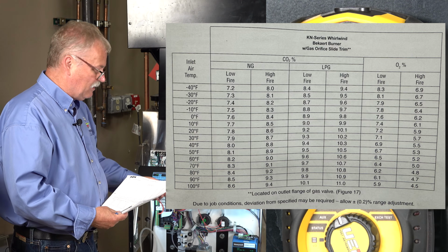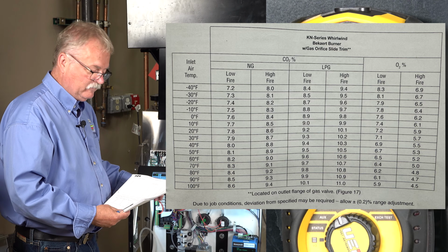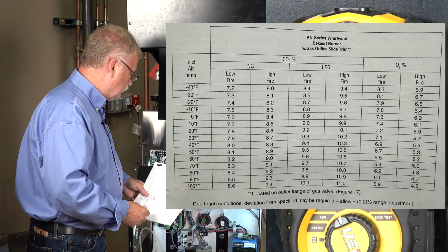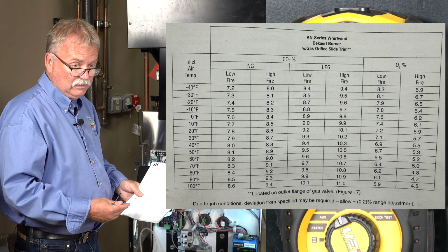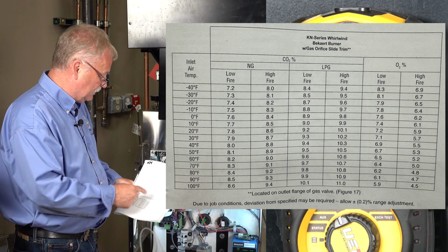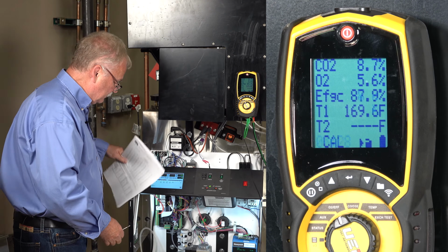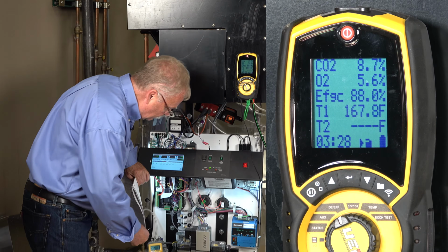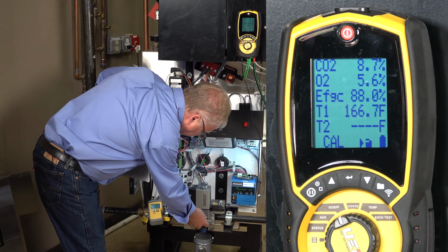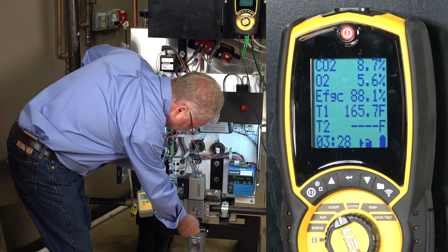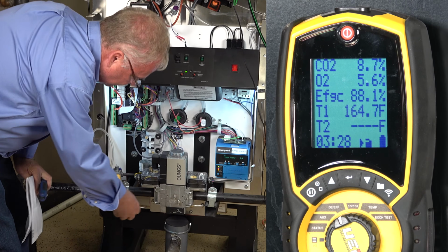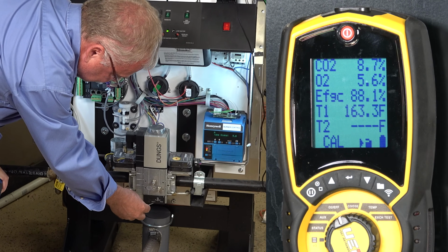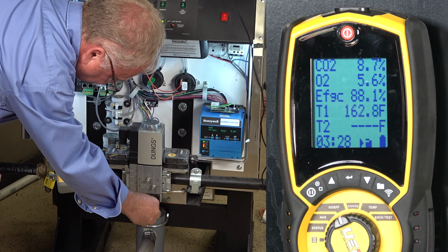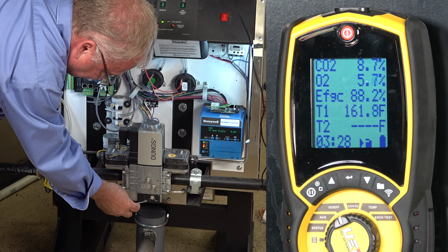As you can hear right now, we're picking up our harmonic noise. We definitely want to get rid of that before we leave and make sure it's still within the ranges that's here. So basically on this Dungs gas valve, our low efficiency or our low combustion adjustment is down here. A lot of times they're called offsets. With this valve, it actually has a little gate on it.